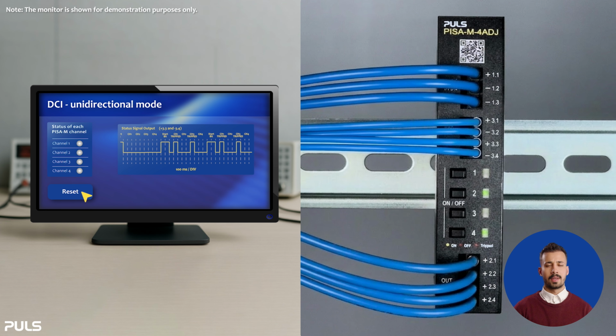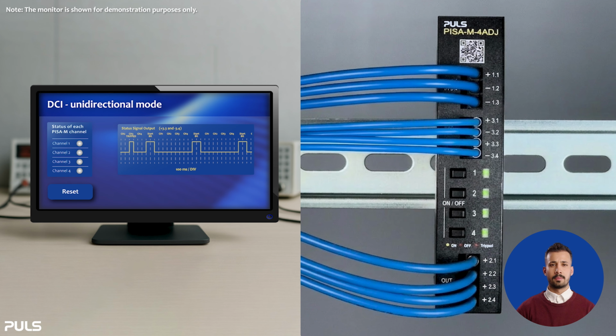To clear the condition, we press the reset button for 1 second. This button is used for reset only. It cannot switch channels on or off, and the reset always applies to all channels simultaneously. The reset sequence only has to be sent once. After the reset has been triggered, the PISA-M first completes the current output sequence. Immediately after that, the reset is accepted and the updated status is transmitted.